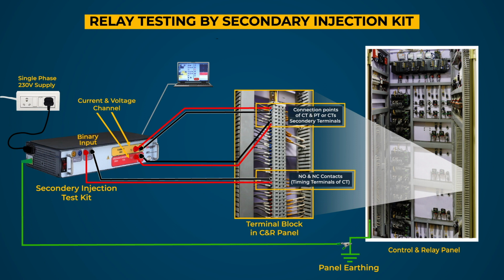On the laptop, start the software and choose the test to be performed on the relay and fill the testing details. Finally, by pressing the test start button, testing begins, and after completion of test, the results are displayed on the screen. This testing data may be recorded for checking the performance and characteristics of relays. If the results are beyond the permissible limits, recalibrate the relay, or if defective, replace the relay.